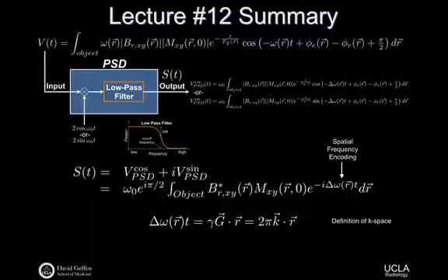We know we can generate these field inhomogeneities in the presence of the B0 field just by adding a gradient. Turn on some gradient, and the field it generates depends on spatial position. How far away are you from isocenter? The most simple expression that we've been working with several times is just the Larmor expression, which says the Larmor frequency, omega 0, is equal to gamma B0. Now we have a slightly different magnetic field, but we can calculate, for example, the frequency offset, delta omega, just gamma times the gradient times the spatial position. So here we've just taken out the B0 term and we talk about the frequency difference at a particular point in space. We were trying to touch on that earlier.